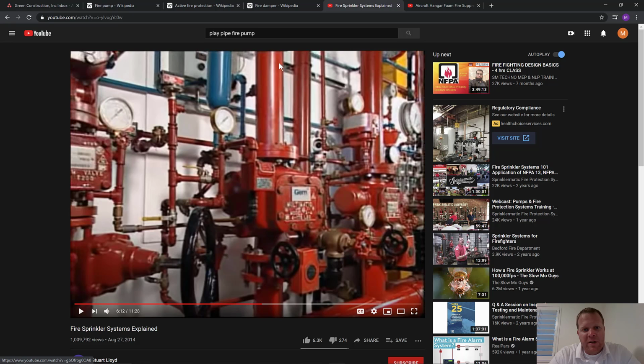One of these could be a dry system - water up to this point, and everything past it stays dry. Not until the fire alarm, a smoke detector or something similar signals to let water flow, will this actually fill the pipe with water. Why would you do that? One reason is that the sprinklers might be in a location where they could freeze, so they won't fill those pipes with water ahead of time. Instead they use a deluge valve that opens and lets water in, controlled by a signal from the fire alarm, though the fire suppression system is what's actually controlling it. Let's see if we can find another example.